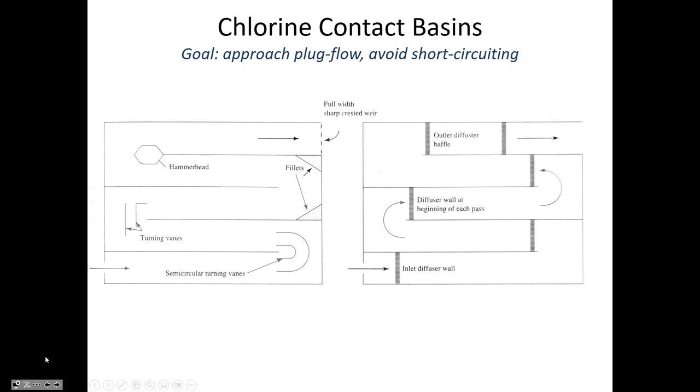You probably remember from environmental engineering different types of reactors. Continuously stirred tank reactors, which are sometimes called completely mixed flow reactors, is at one extreme where water is immediately dispersed and continually mixed. At the other end of the spectrum is a plug flow reactor, where there's no mixing of the particles as it travels through the reactor. Typically plug flow reactors are long and skinny to achieve that and limit the amount of dispersal.